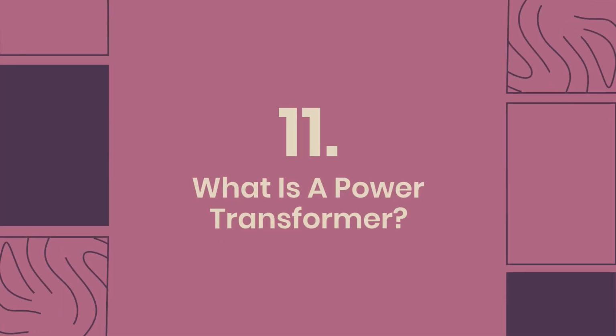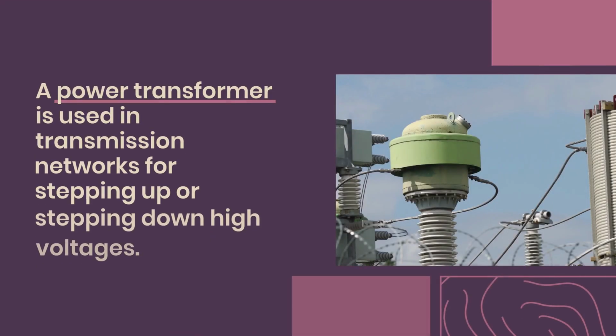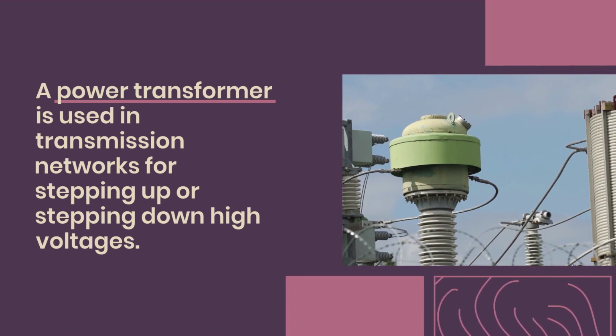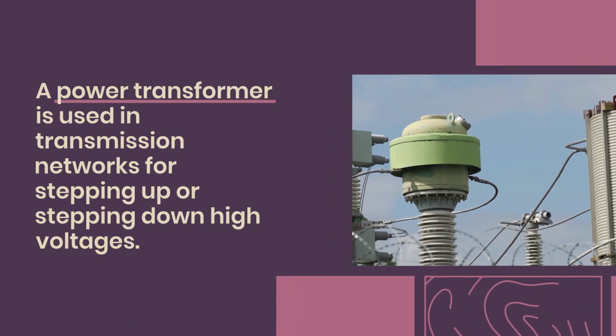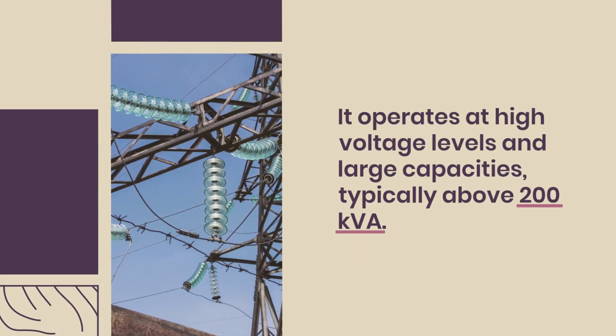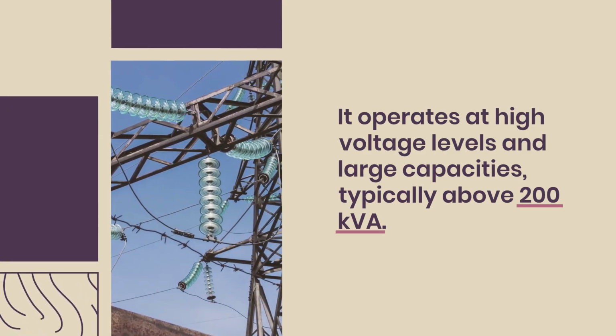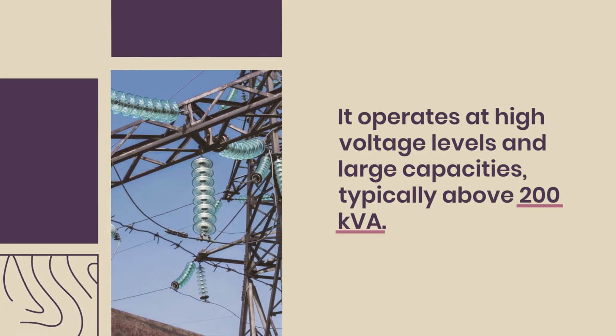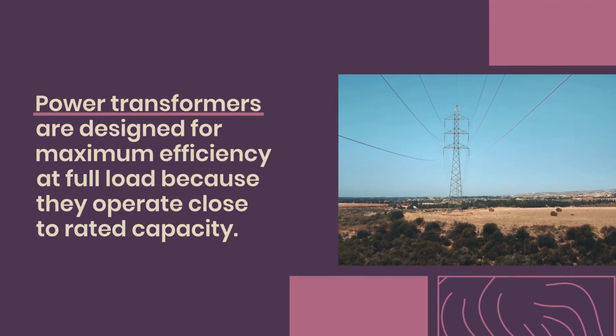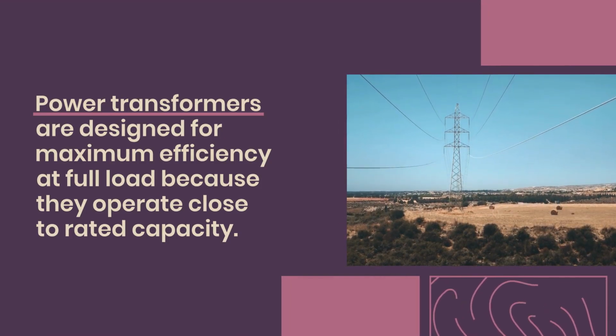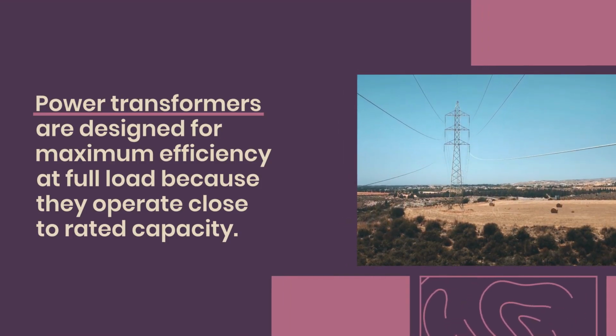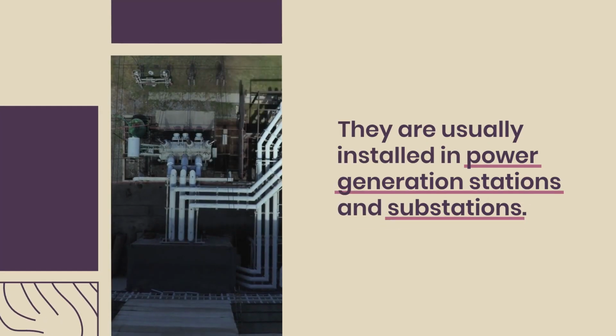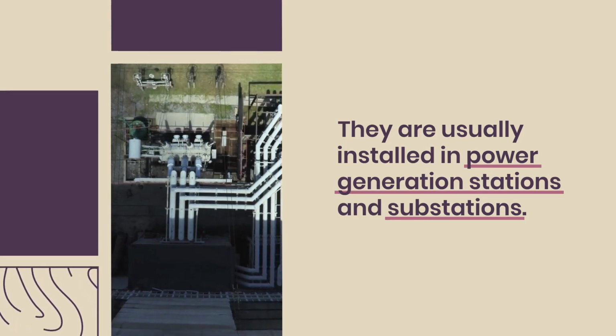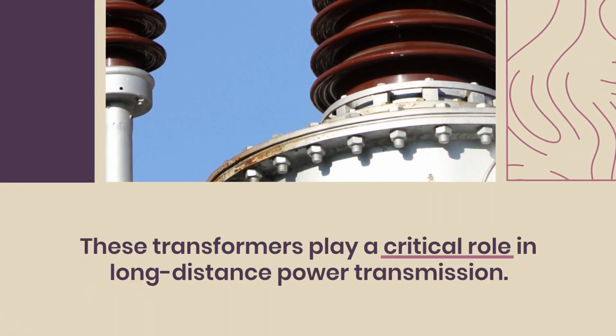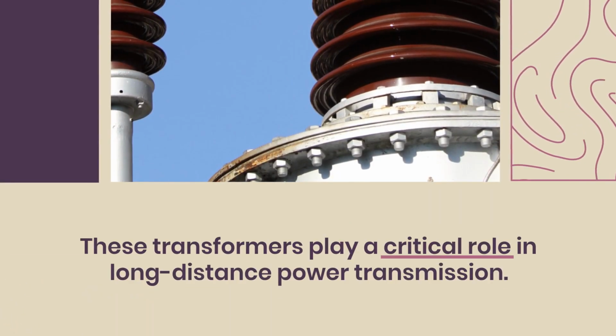11. What is a power transformer? A power transformer is used in transmission networks for stepping up or stepping down high voltages. It operates at high voltage levels and large capacities, typically above 200 kVA. Power transformers are designed for maximum efficiency at full load because they operate close to rated capacity. They are usually installed in power generation stations and substations. These transformers play a critical role in long-distance power transmission.